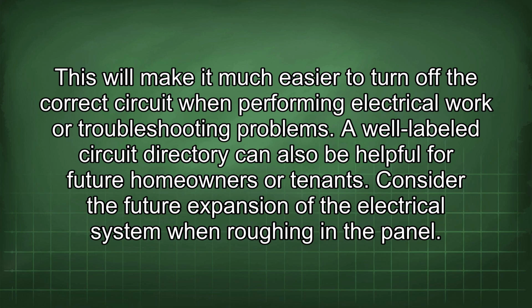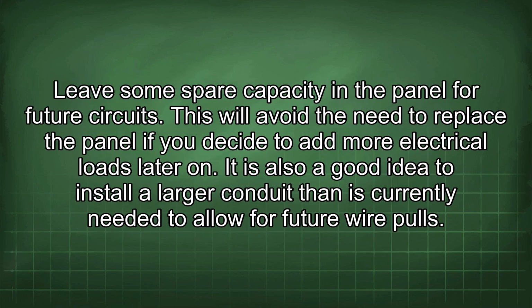Consider the future expansion of the electrical system when roughing in the panel. Leave some spare capacity in the panel for future circuits. This will avoid the need to replace the panel if you decide to add more electrical loads later on. It is also a good idea to install a larger conduit than is currently needed to allow for future wire pulls.